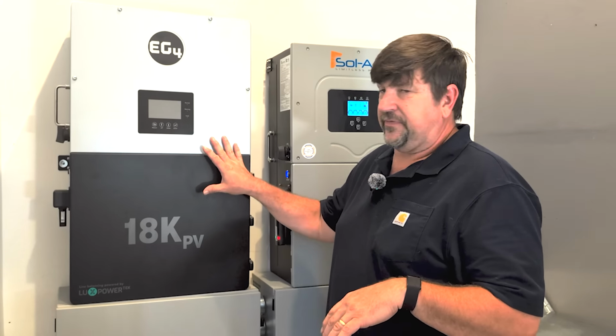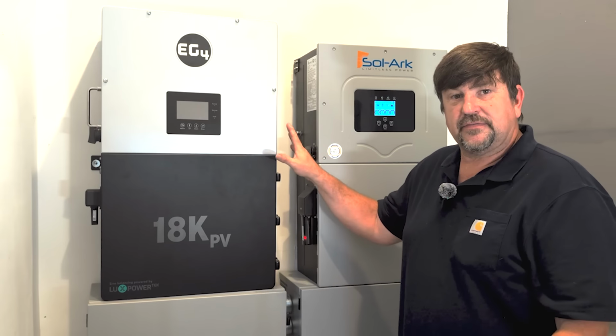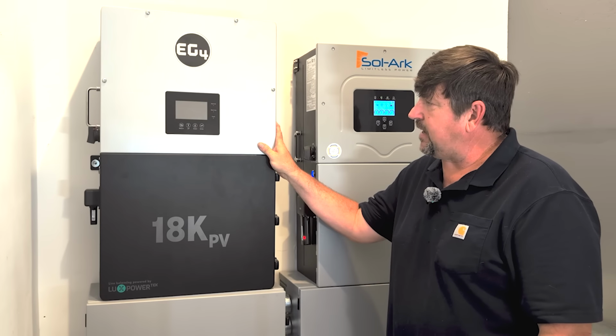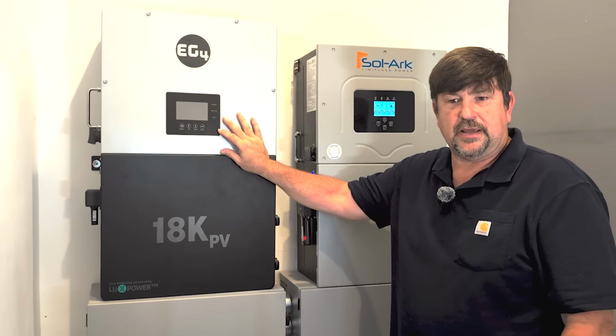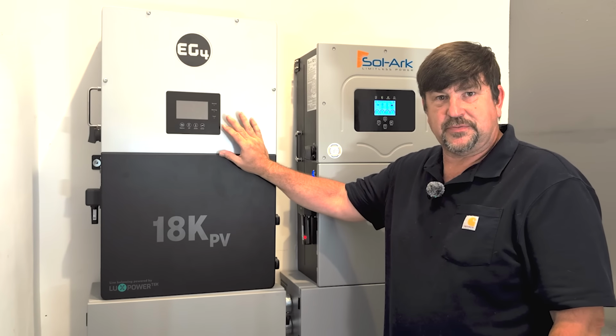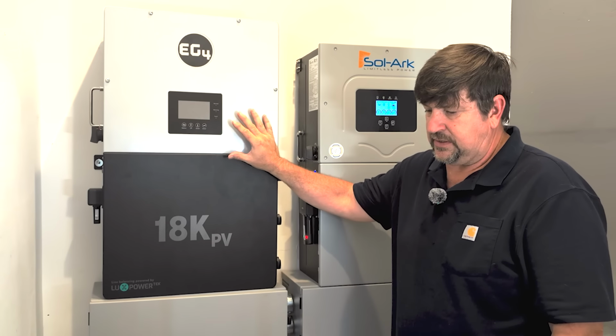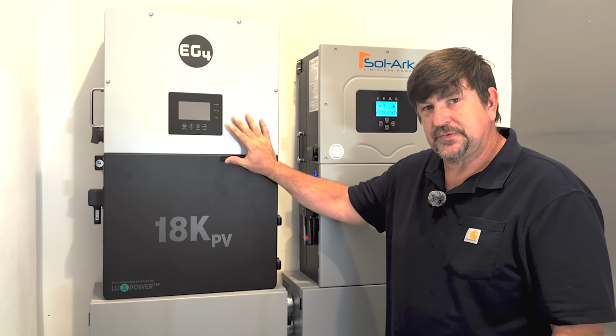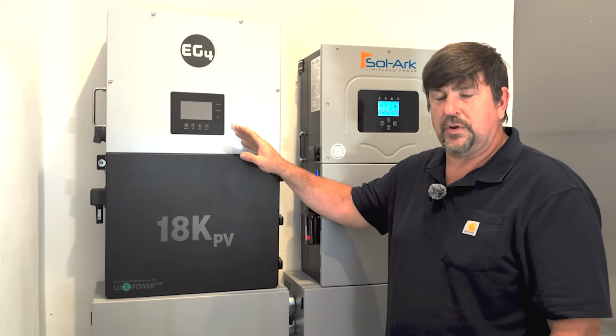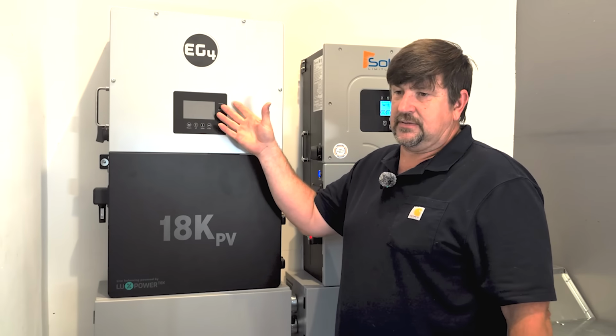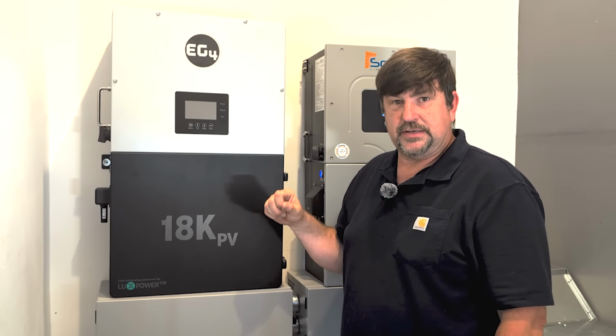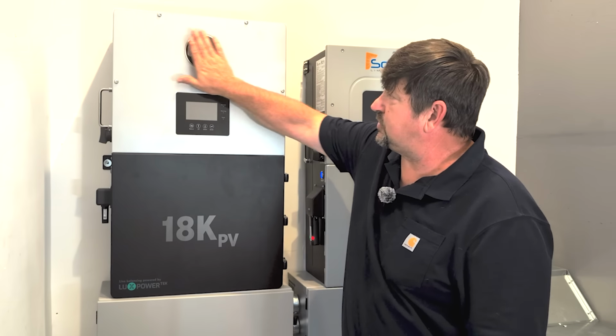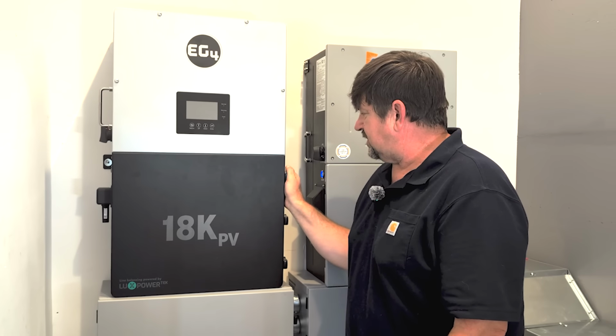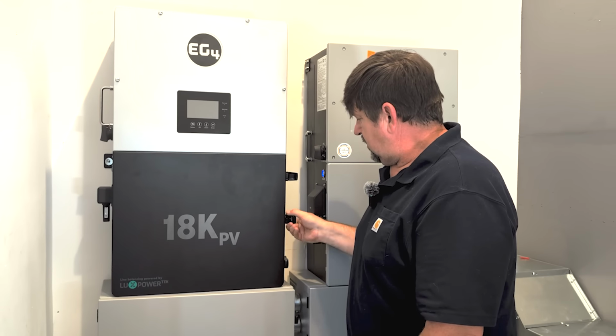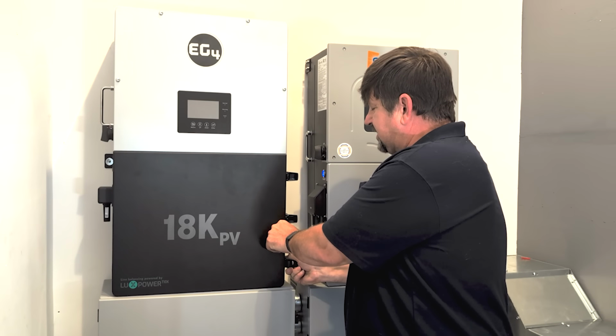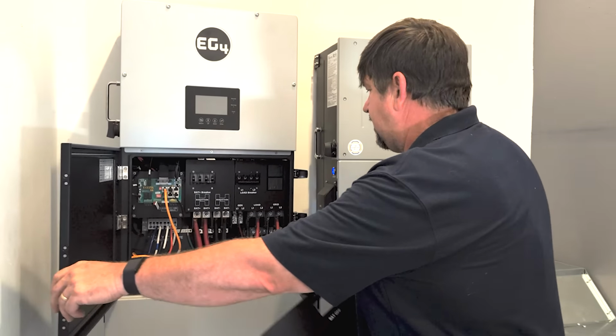Okay, just as a wrap, you'll see the Sol-Ark is on. We're going to do the same test we performed on the EG4 18K-PV. We did have to shut that one down — we were worried about overtemps. We had 3 temperature faults with that machine. EG4's Signature Solar tech team said 120 is supposed to be when it shuts down, but according to the display, it went up to 131 degrees, super hot to touch on the front. So it made me nervous, and we uninstalled it. Now we're going to run the same tests on the Sol-Ark 15K.